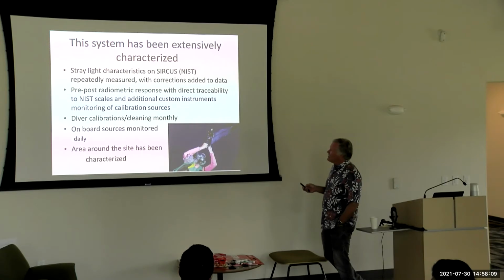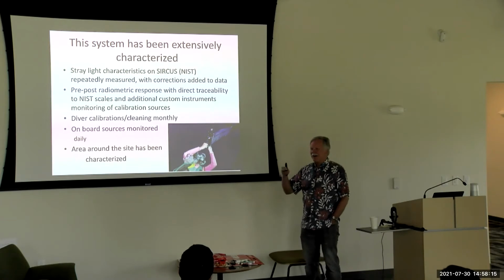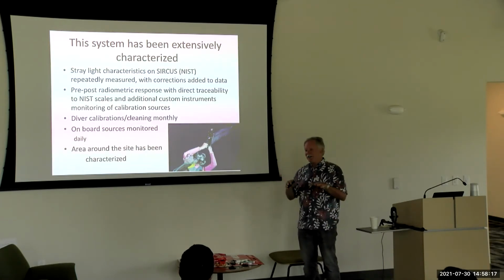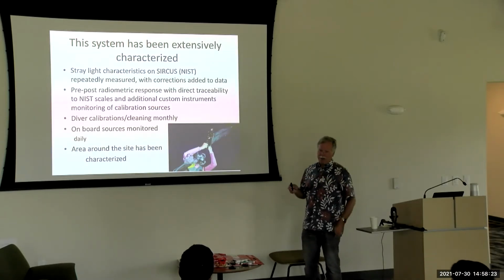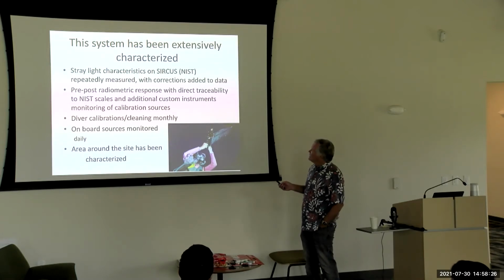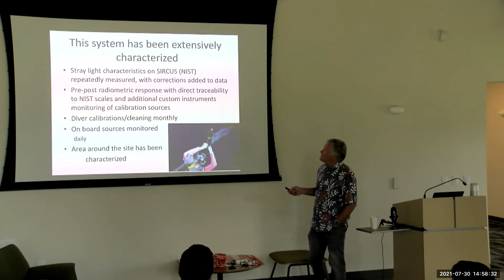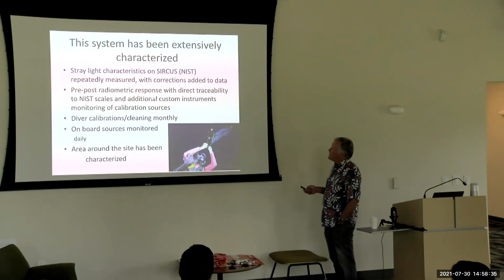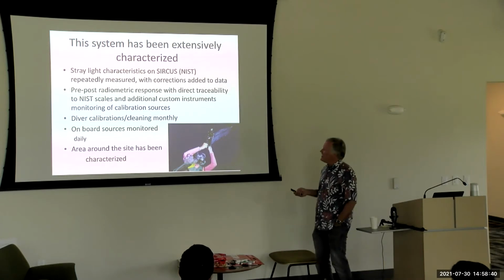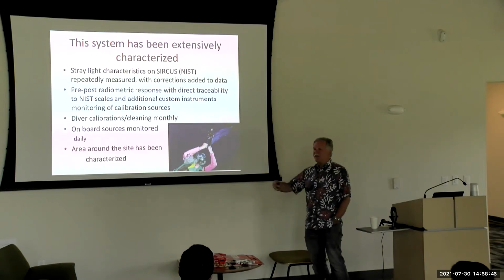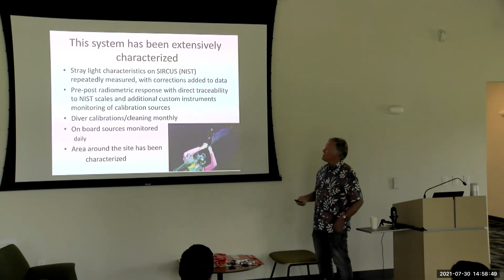The stray light source is at NIST. I think I answered a question about it. It's a laser system that is set up so you pick whatever line you want, and you just work your way through the spectrum. I'll show you some data from that a little bit later. So stray light is characterized. We do pre and post radiometric response, directly traceable to NIST. We have a bunch of other custom instruments that are in Hawaii that monitor the sources to make sure that we're staying stable between the times when the sources go back to NIST.